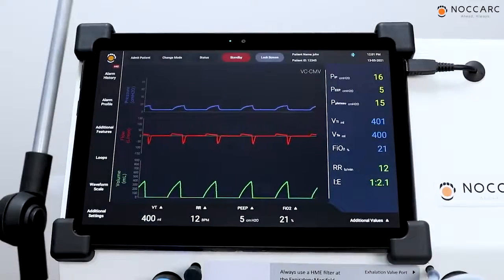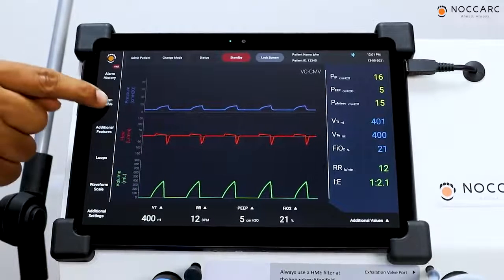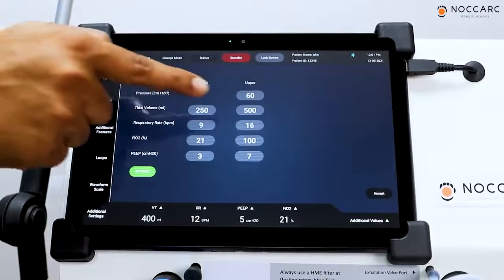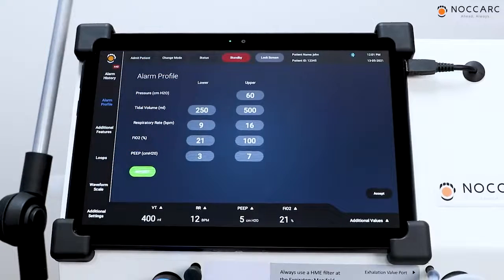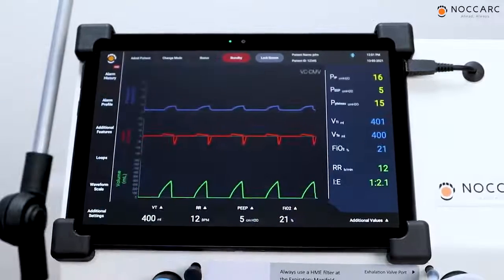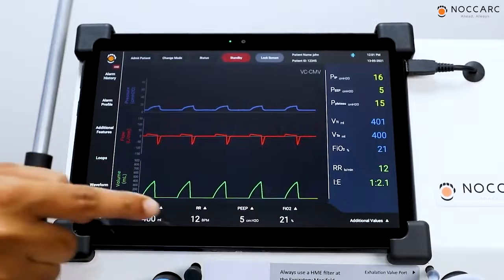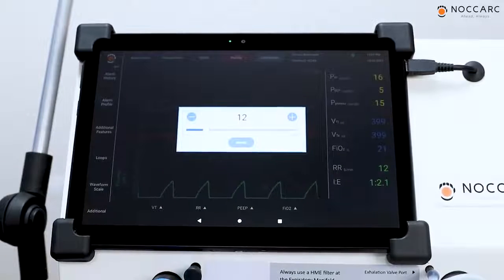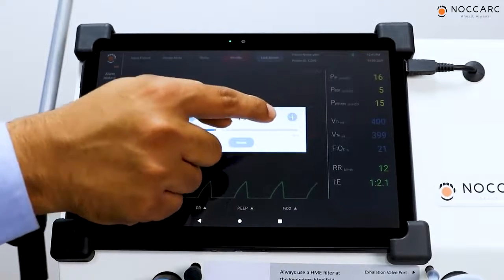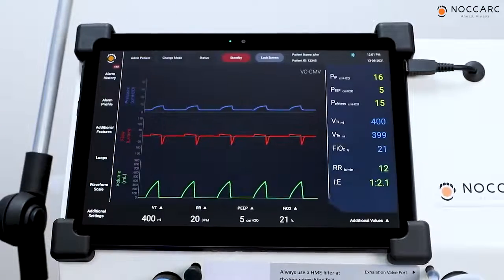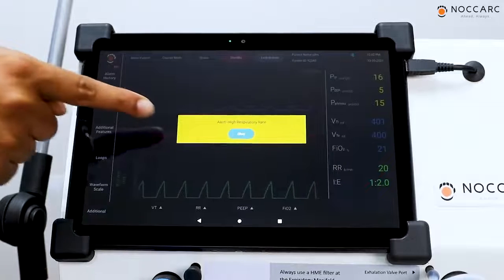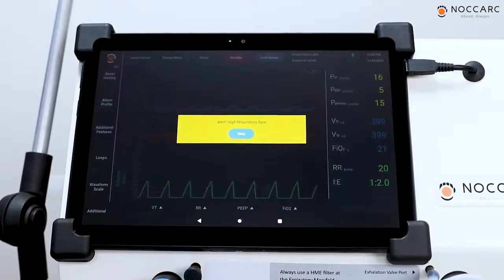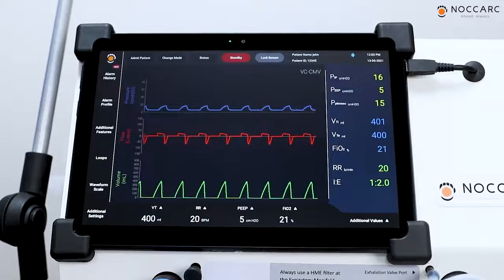To test high respiratory rate alarm, press on alarm profile. The upper limit for respiratory rate is 16. Press on accept. Now press on this set RR option and increase the RR more than 16 and accept it. Here you can see high respiratory rate alarm is showing on the screen. That indicates respiratory rate exceeds the limit for alarm profile.